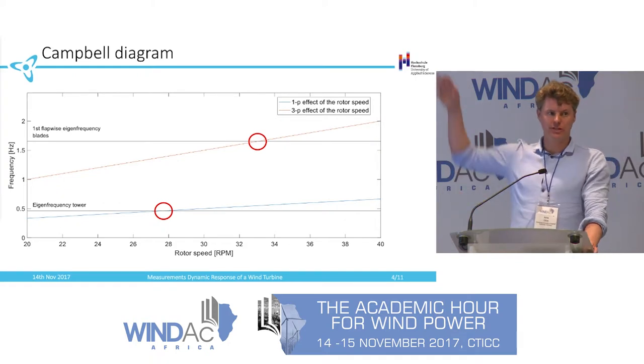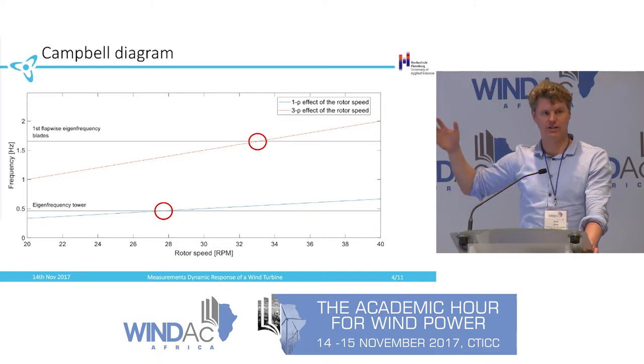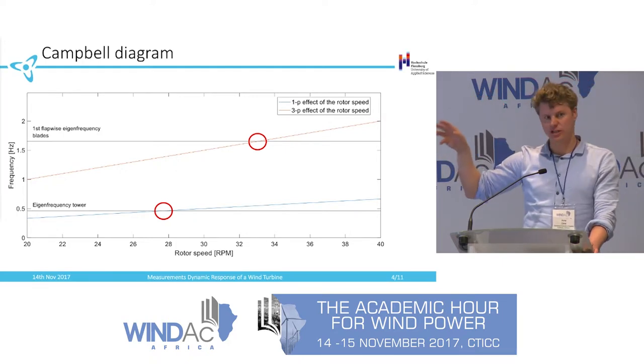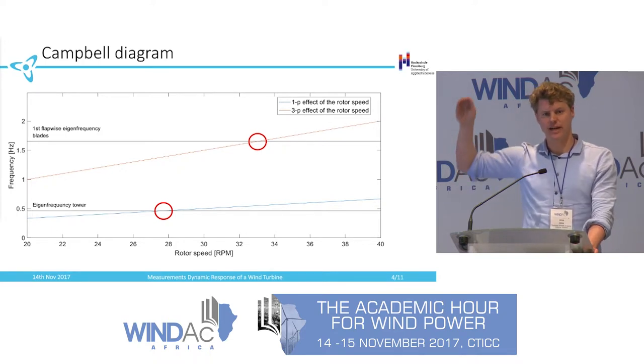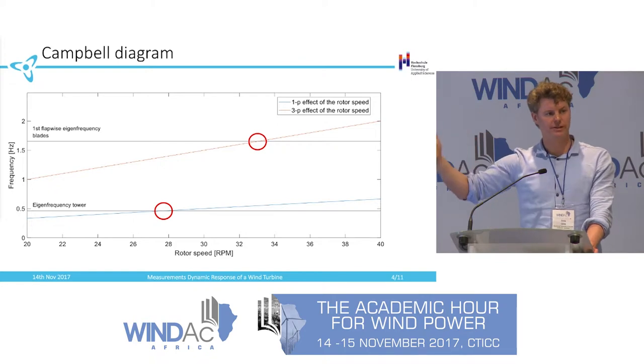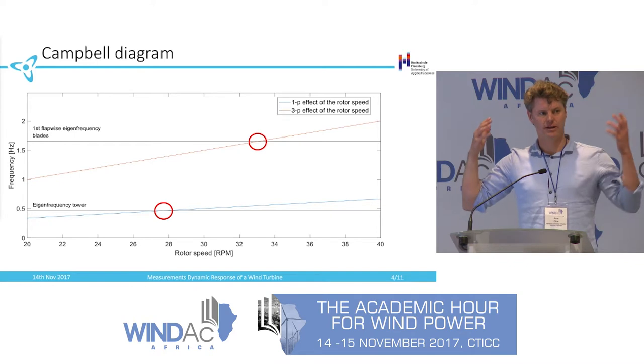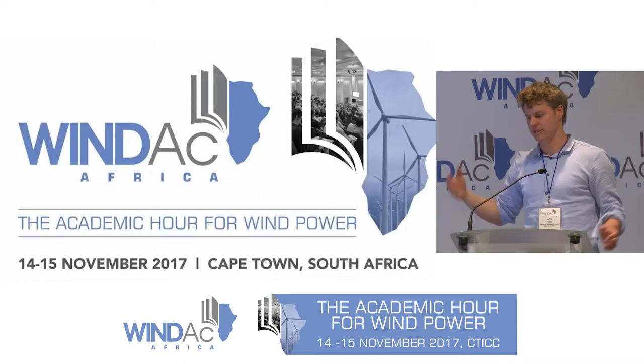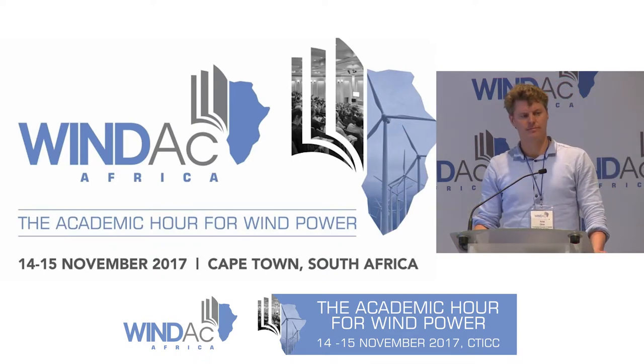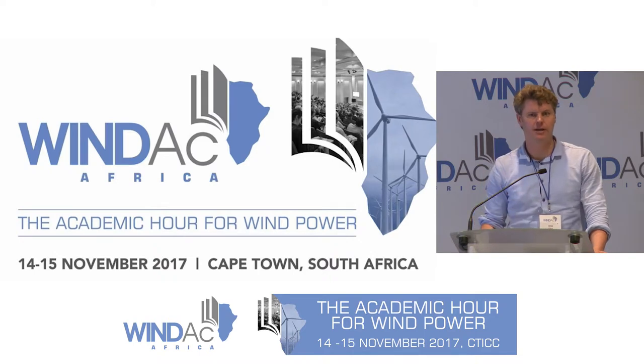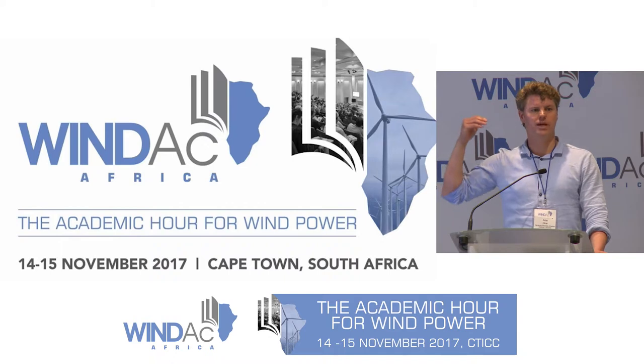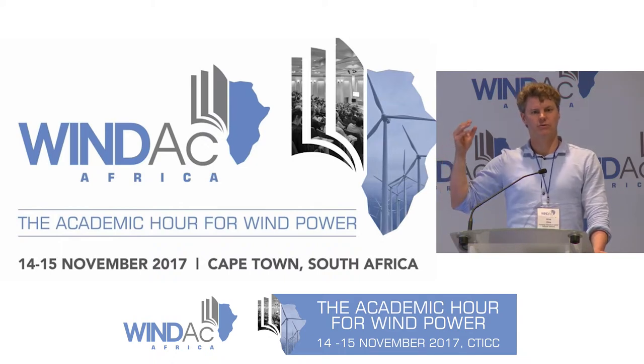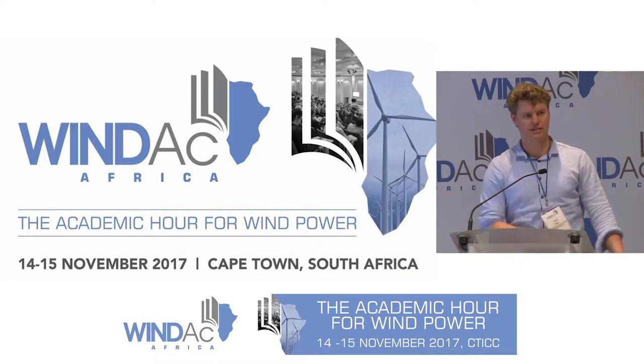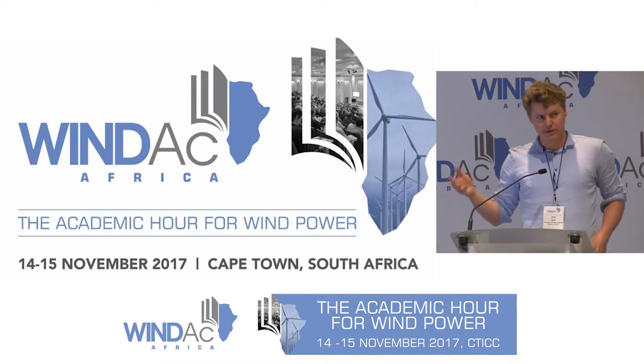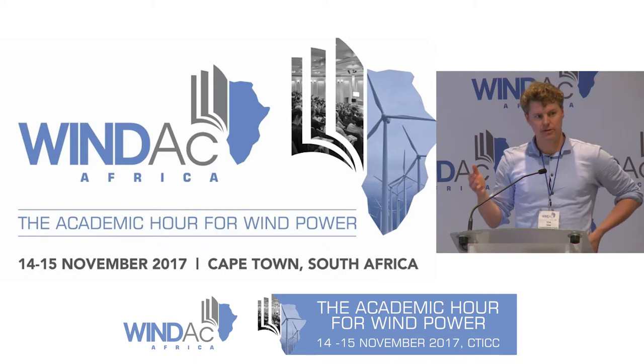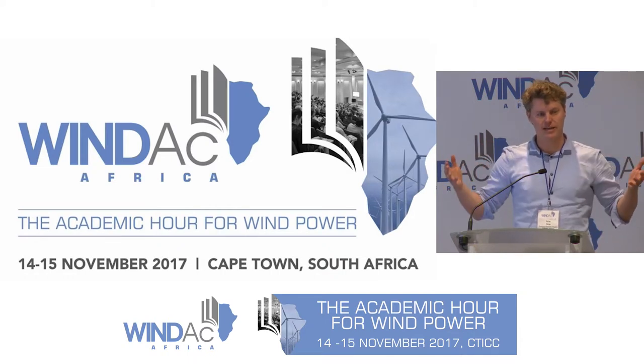Okay, what you would usually do, or what we would expect the turbine manufacturer to do, these situations are not easy to avoid. So you can shift this eigenfrequency by the design, but that usually means you have to put in more material. So it's a matter of cost, making your tower heavier, putting more steel in. That's something you want to avoid. So what we expected at first when we saw the Campbell diagram, was that Enercon actually put measures in the control system in place to minimize what is called the dwell time in these situations. So if I get into a resonance situation, that is actually not a problem. It's only a problem if I stay there for a longer time, so a couple of seconds or even longer.